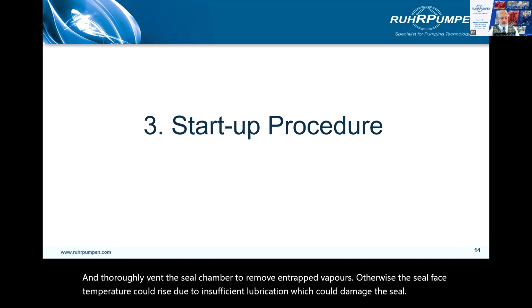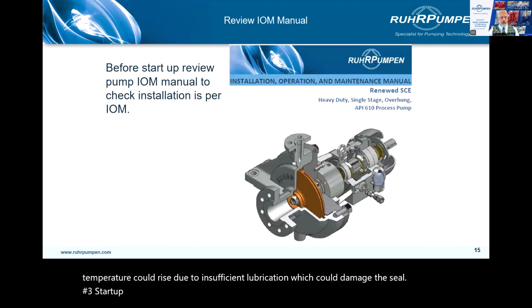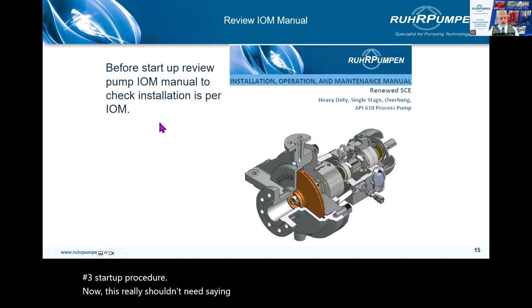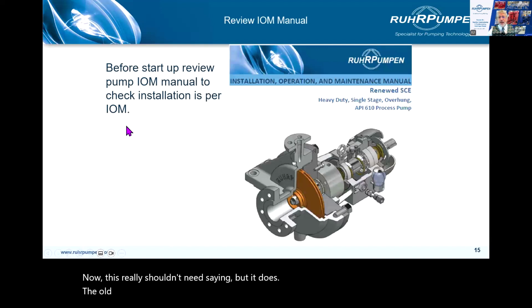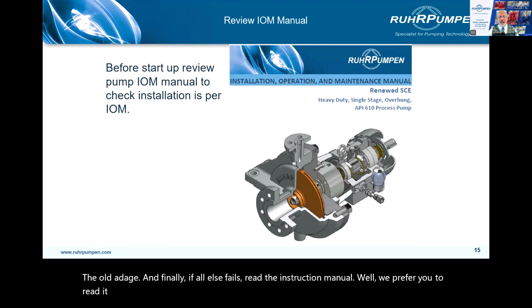Number 3, startup procedure. Now, this really shouldn't need saying, but it does. You know the old adage, finally, if all else fails, read the instruction manual. Well, we prefer you to read it in advance. And the other thing you need when you do the commissioning is you must have the pump curve there. We'll come to that.